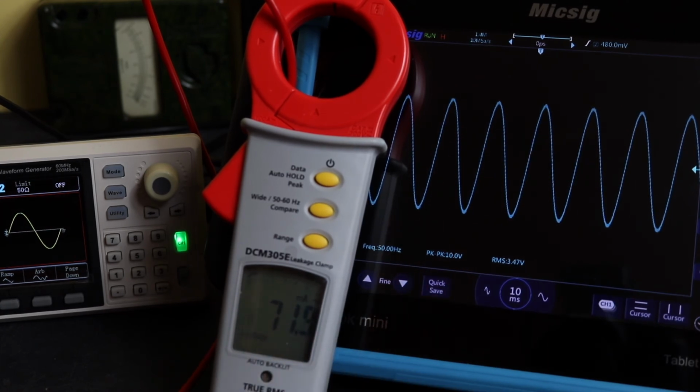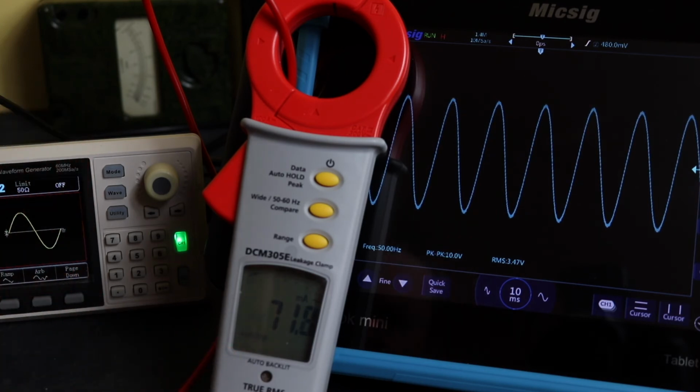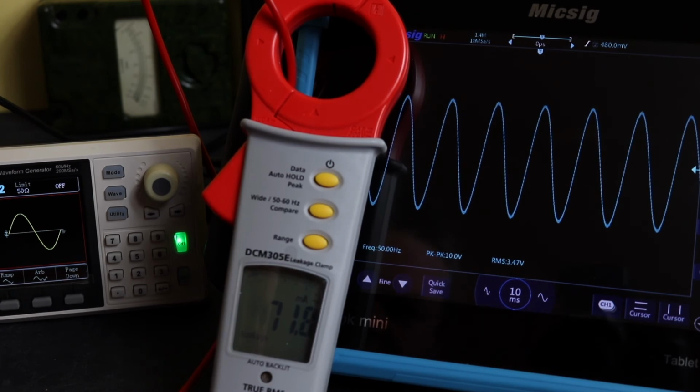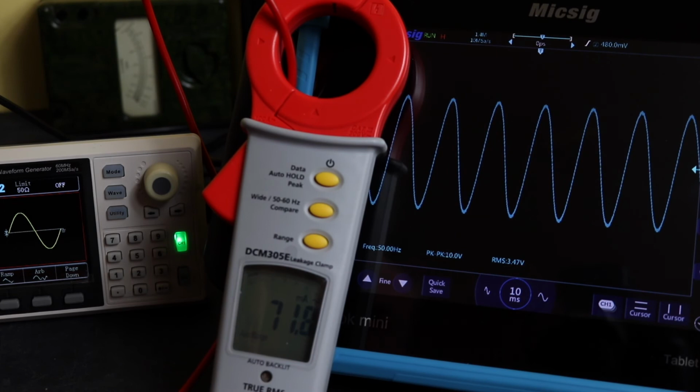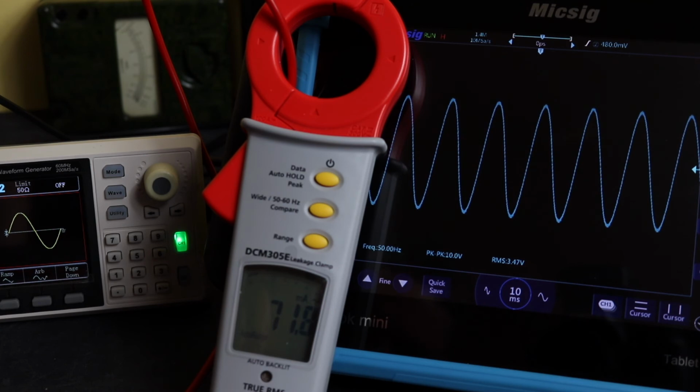It could be a combination of a current limit on the output of this, but it's also to do with the fact you can never really fully trust what the output voltage is of these on your actual load that you've got connected to it. It can change depending on how you set the loading of the unit to make sure that it does match the load that you're applying, and that's the important thing that you need to do.